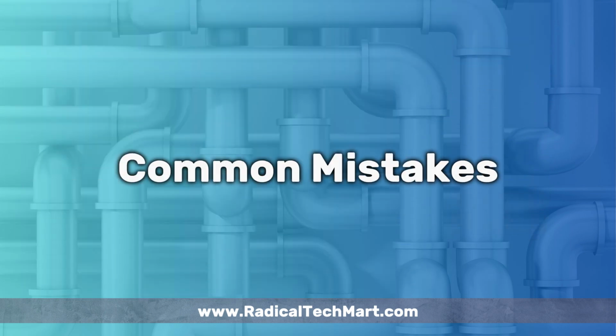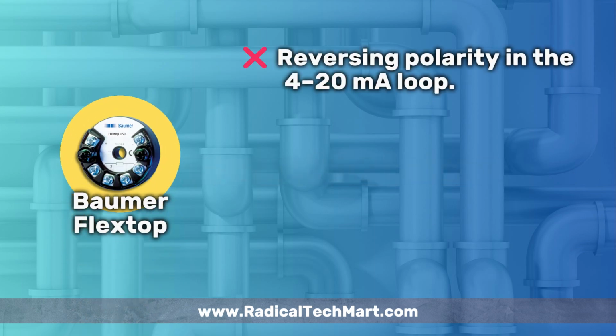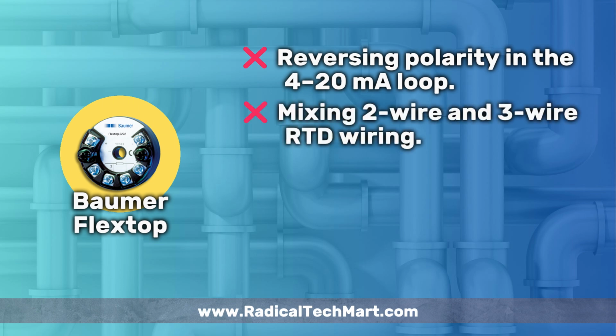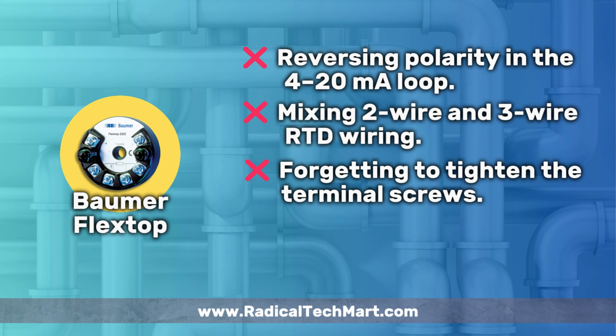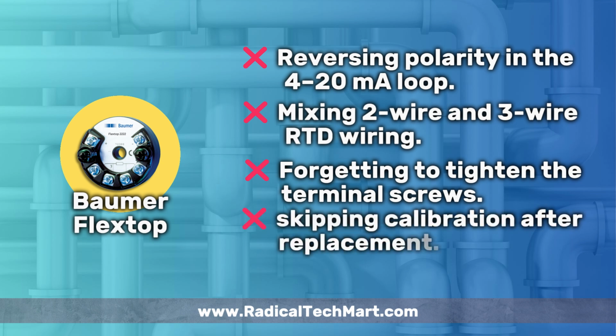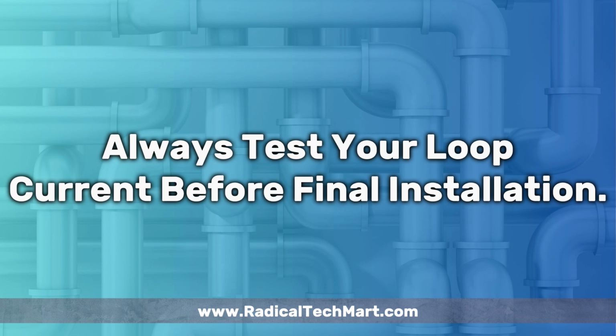Now let's talk about common mistakes engineers often make. Reversing polarity in the 4 to 20 mA loop. This can prevent output completely. Mixing 2-wire and 3-wire RTD wiring. Always match the input configuration. Forgetting to tighten the terminal screws, loose contacts create erratic readings. And skipping calibration after replacement. Even small errors affect accuracy. Always test your loop current before final installation.